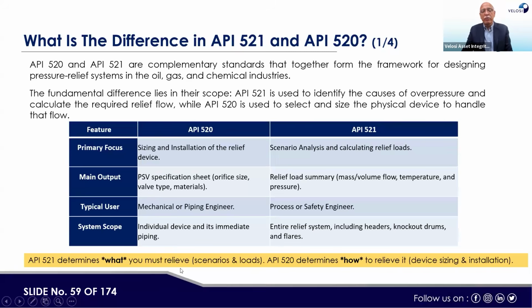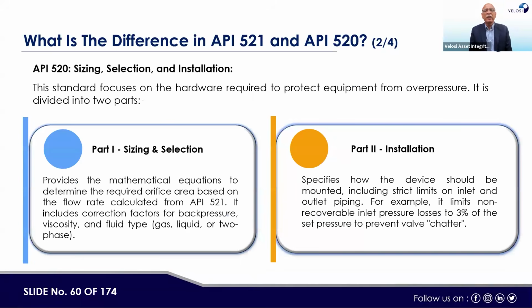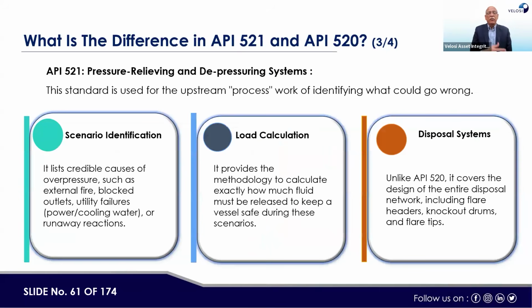521 determines what you must relieve, the scenario or the loads. 520 determines how to relieve it, device sizing and installation. This is very important, we should remember this difference between API 520 and 521. Here, part 1 is sizing, part 2 is installation. I explained earlier, part 1 is a guideline on how the PSV should be sized, and part 2 is how the PSV should be selected and installed. Then in 521, there is scenario identification, load calculations, and disposal system.